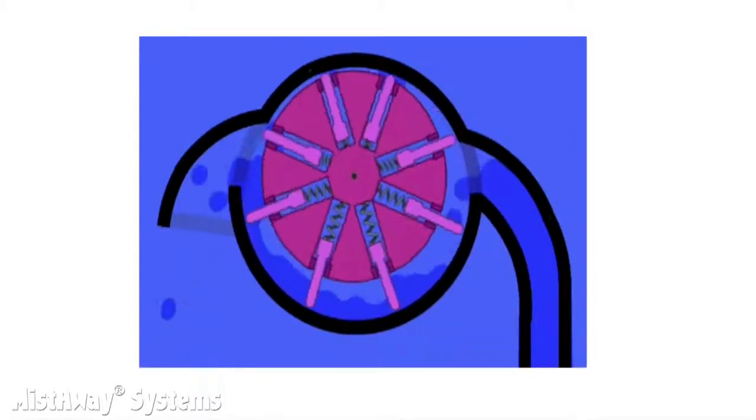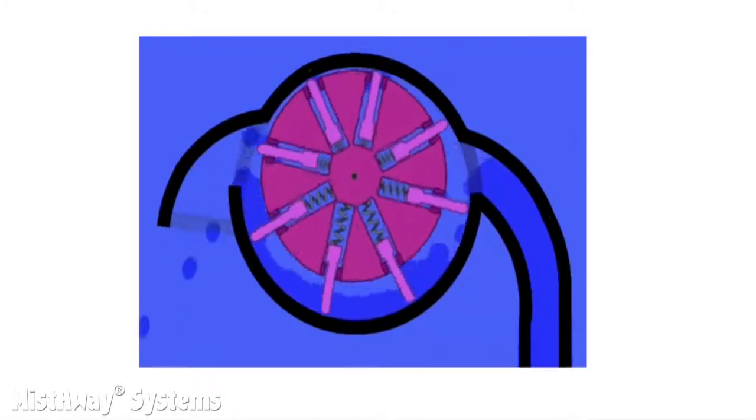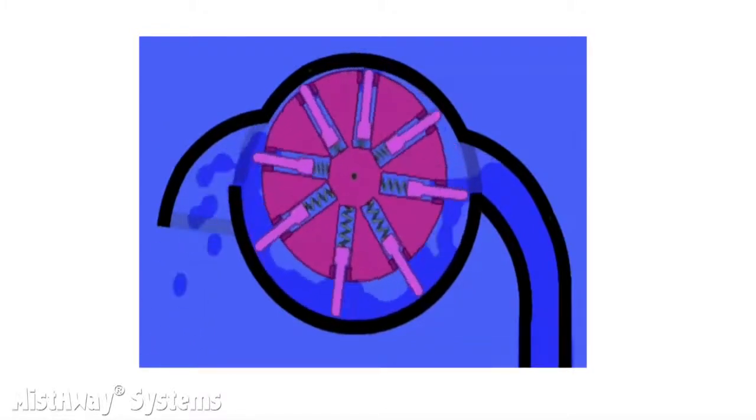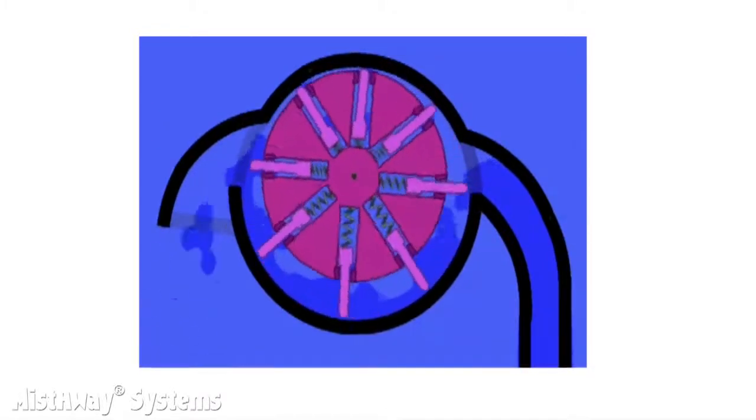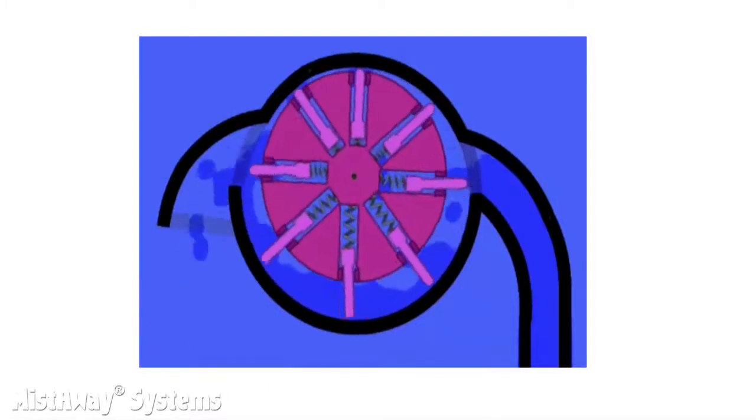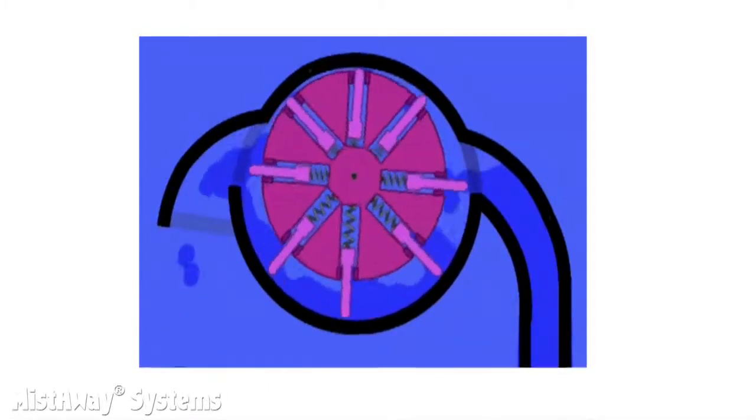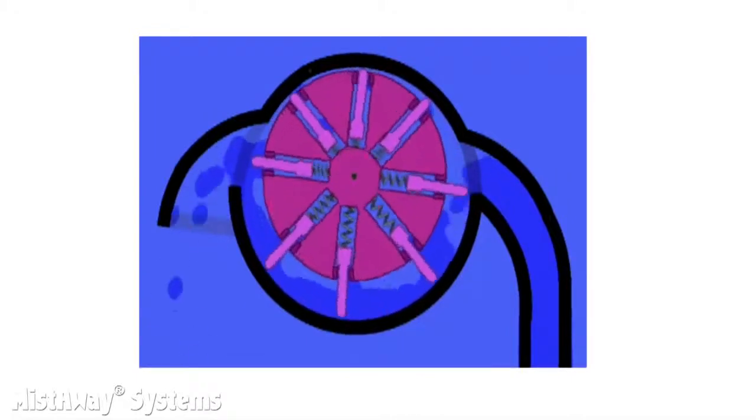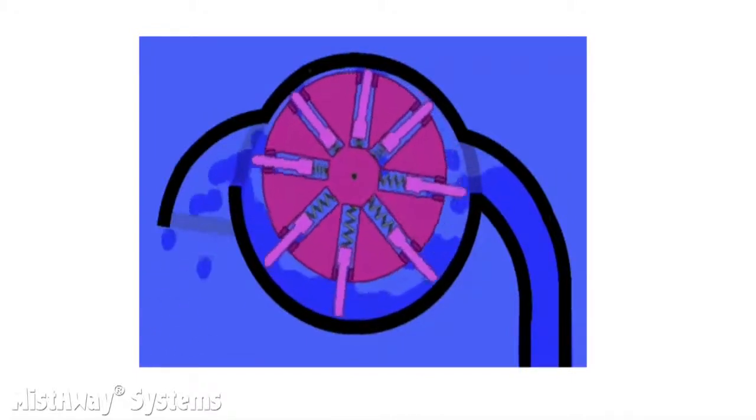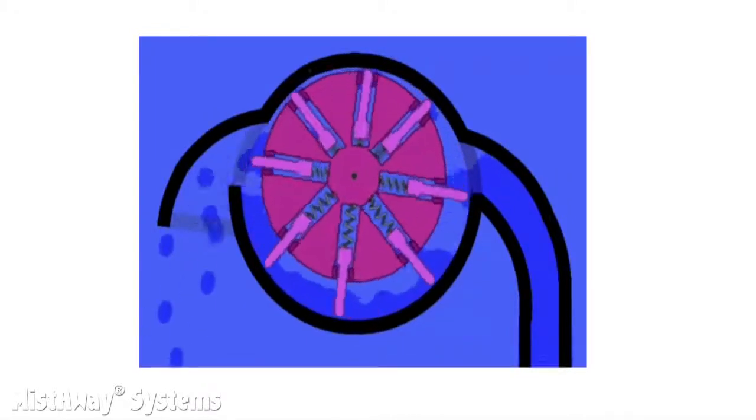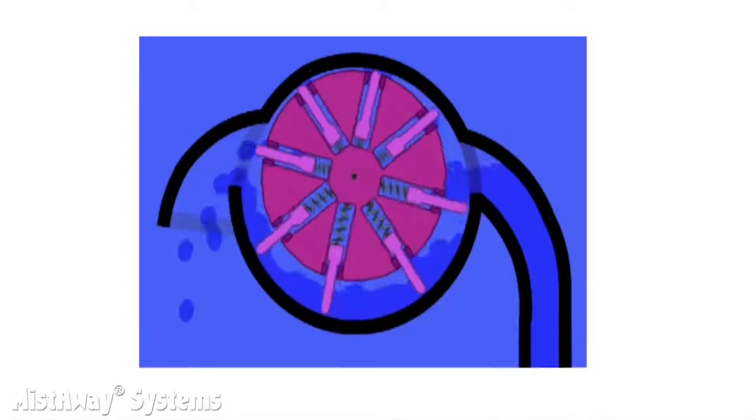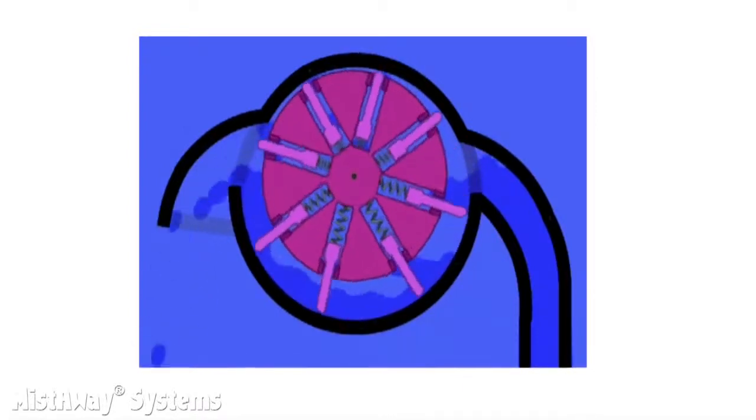Note that the size of the chambers change during the rotation. On the intake side, you'll see that the size of the chambers created by the vanes increases as the rotor moves clockwise past the inlet. This creates a suction that pulls fluid into the pump. As the vanes move toward the discharge side, the chamber decreases in size, adding pressure to the fluid as it exits the pump.